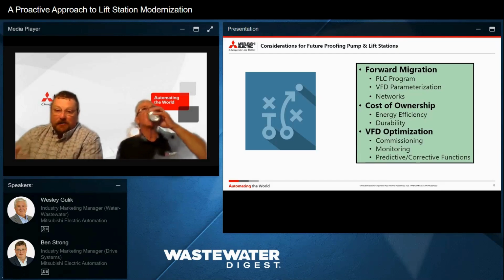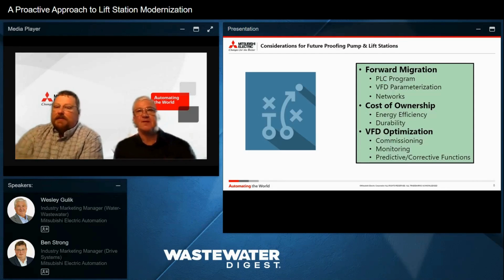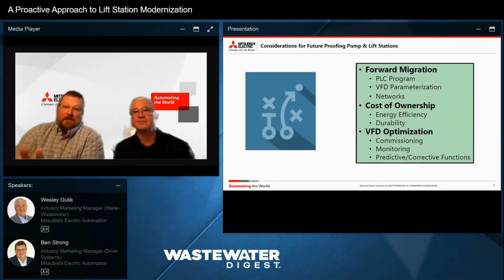To put that in context, why should I care? The average life of the mechanical system of a lift station is 50 years. So in the 50 years of service of that device, you should expect to upgrade the controls 2.5 times, depending on where you hit and how reliable the products you use to upgrade those lift stations are. Another consideration is networks. There are tons and tons of municipalities still using serial. If you had a vision into the future, would you have implemented Ethernet 10 or 15 years ago for your municipality? So that's something to think about.